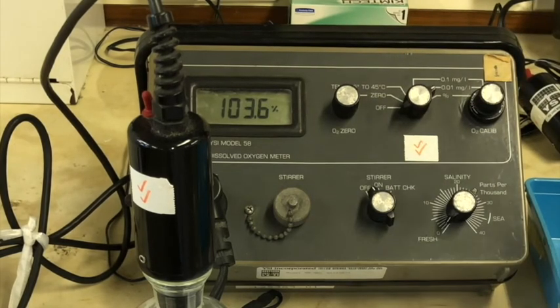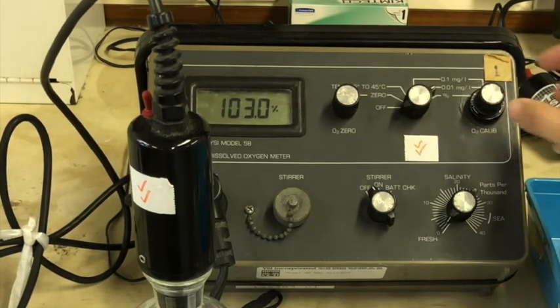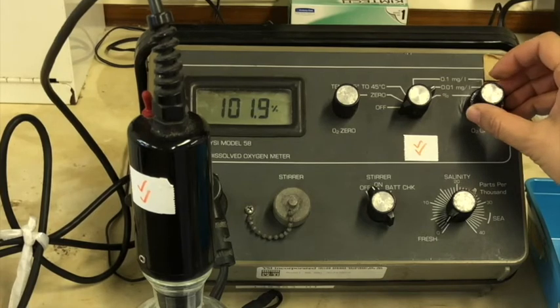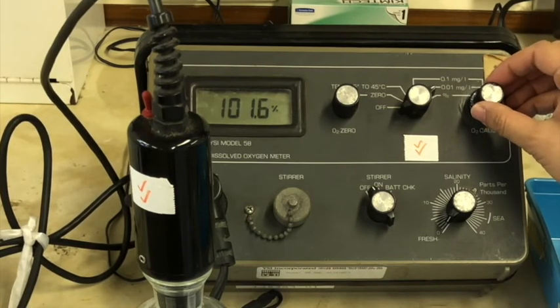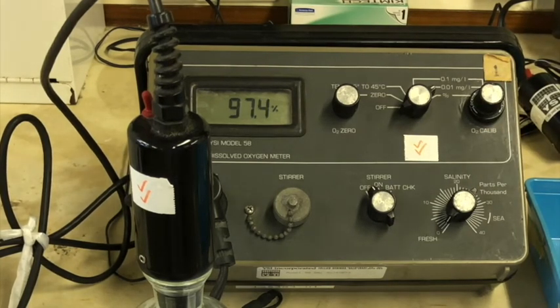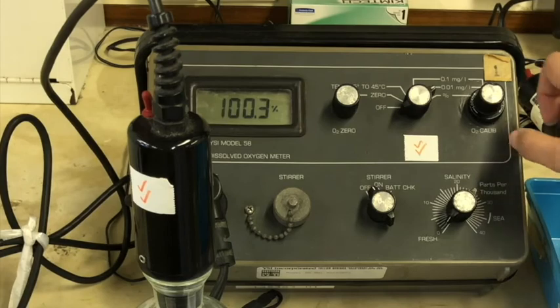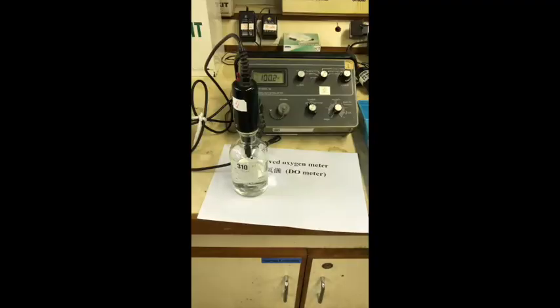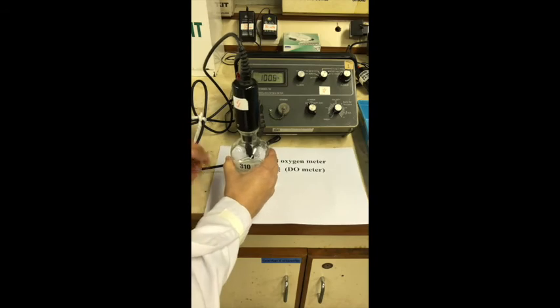The fluctuation of the readings indicates the oxygen membrane is getting older. The knob can be adjusted clockwise or anti-clockwise to get the number to reach 100%. As the fluctuation gets small and the number is around 100%, it means the setting for saturation is finished. You need to lock the knob after setting 100% and change over for the sample measurement.